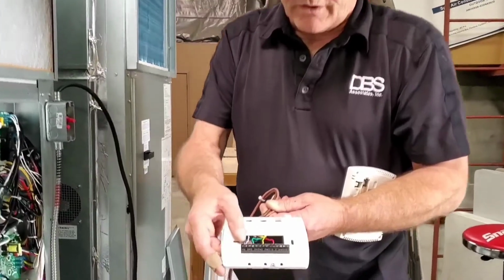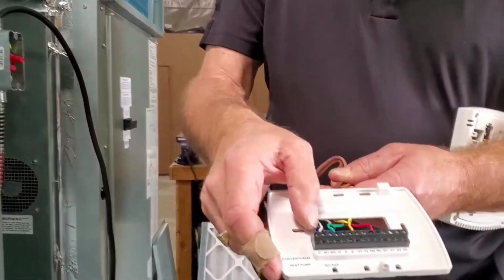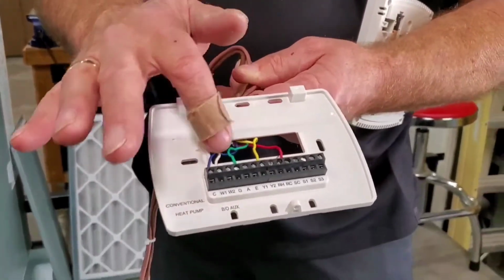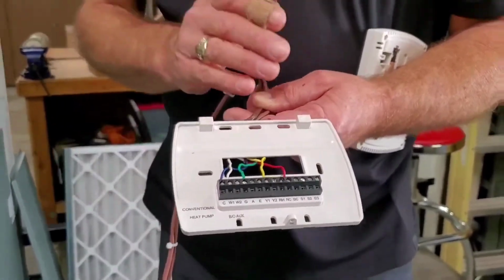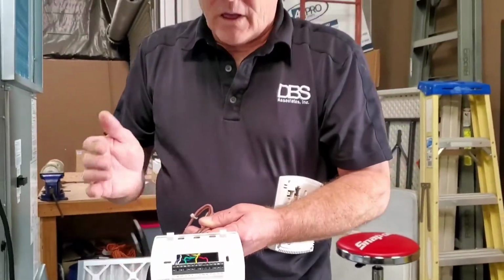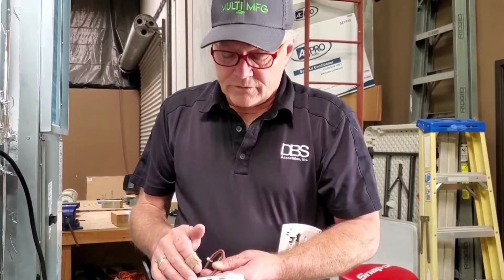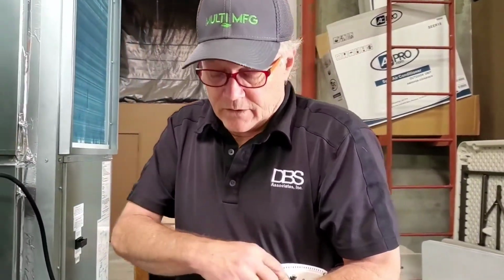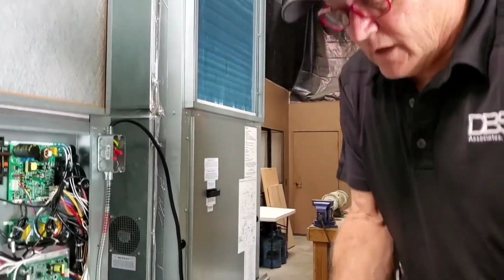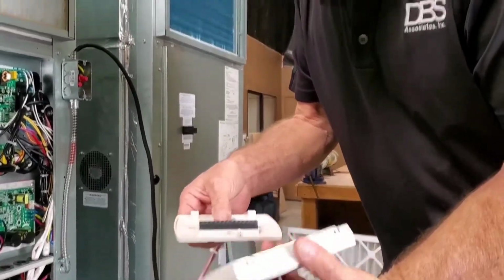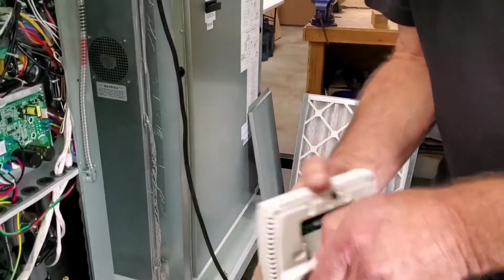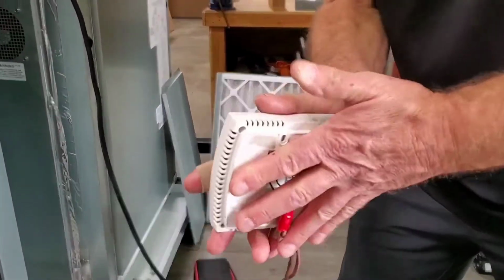So you do not want to energize O and B terminals like an existing thermostat. But if you have a Verdant system in your hotel, that can be switched over. Just get a hold of us. We'll tell you how to do that. So that's the wiring. So basically, this thermostat is going to come with every unit. Let me put it together and we'll turn it on. I'll show you what happens when you first energize this thing in heat mode.